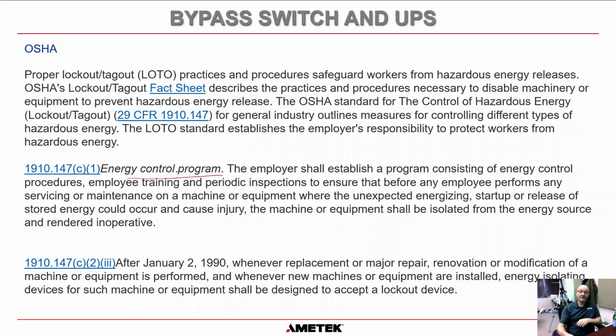And more specifically, one of the rules that many people don't understand is 1910.147(c)(2)(iii). After January 2nd, 1990, whenever the replacement or major repair of any piece of equipment has been performed, or when new machines or equipment are installed, energy isolating devices for such machines or equipment shall be designed to accept a lockout device. So basically, whenever you do any major maintenance or install new equipment, you should be able to lock out and tag out that system and make it volt free. That's pretty much what that rule is saying.